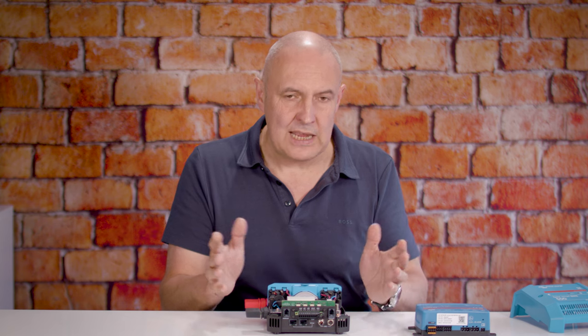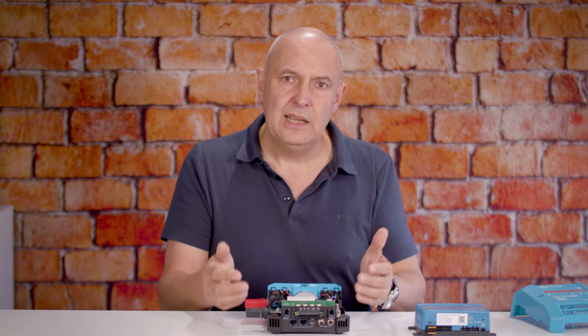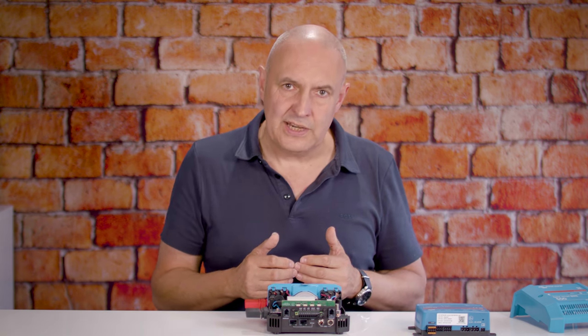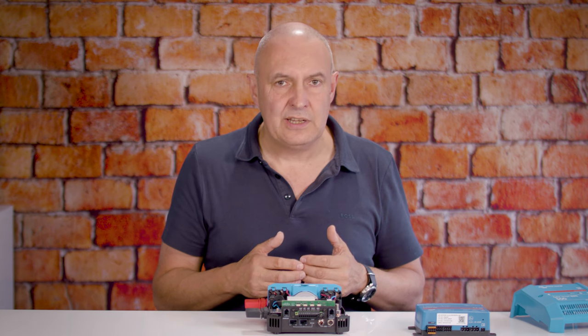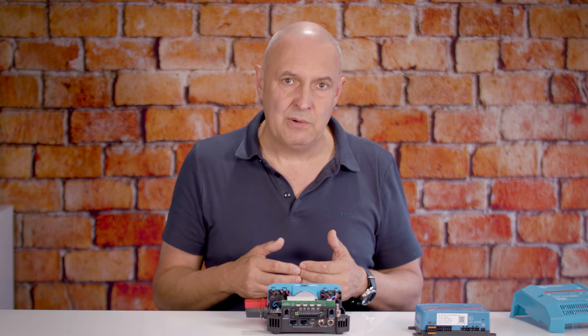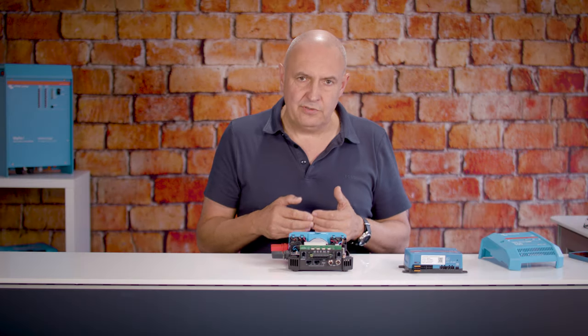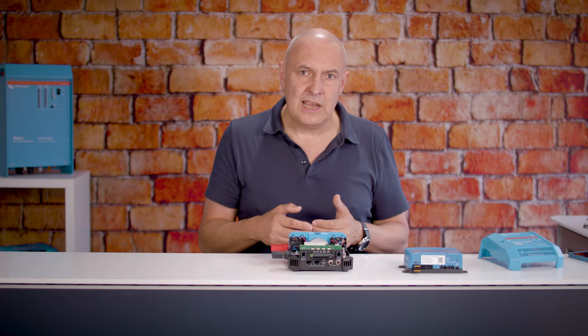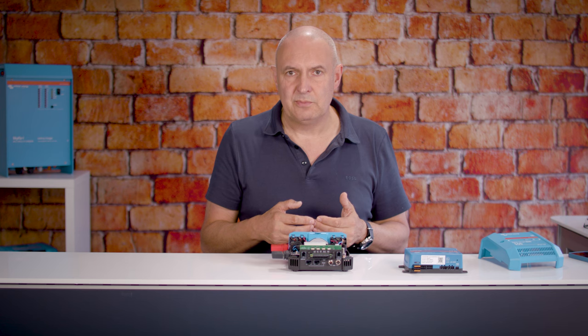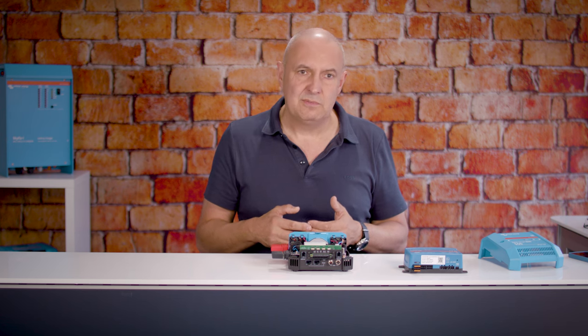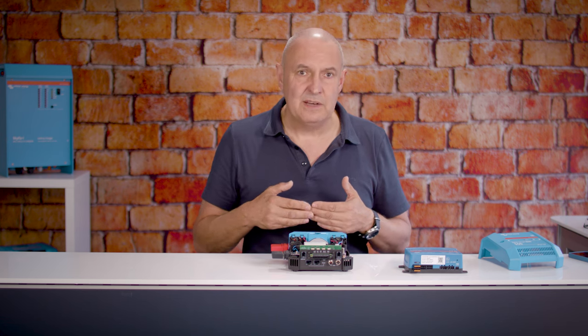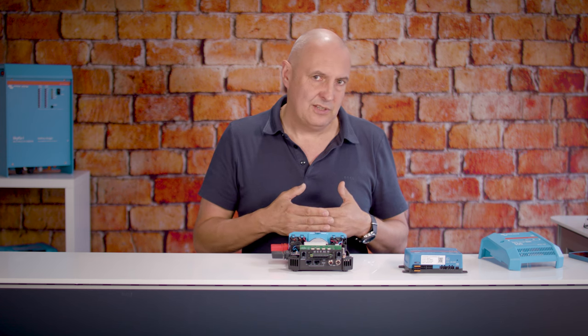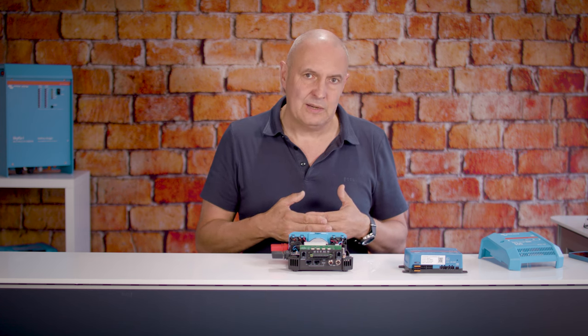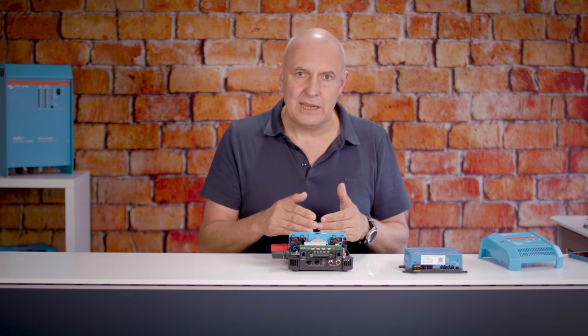So if I make an example, in the event that we're getting quite low on state of charge and we're approaching the voltage limit that's allowable on the batteries, the first thing that we'll get is a trigger to say that we should stop discharging. And this is to give us a bit of a buffer so that some essential circuits can continue to operate before we actually hit the main contactor.